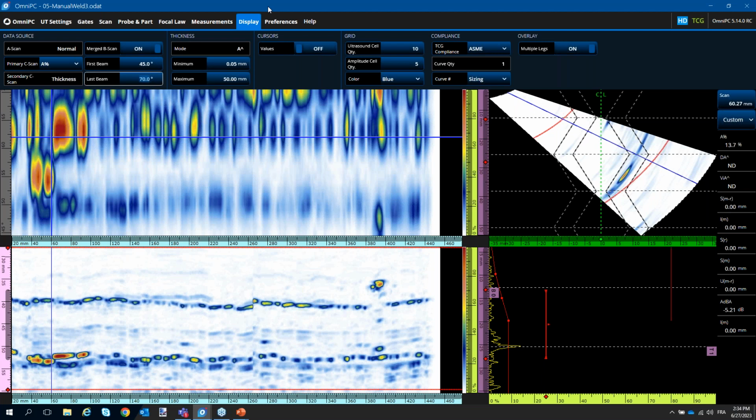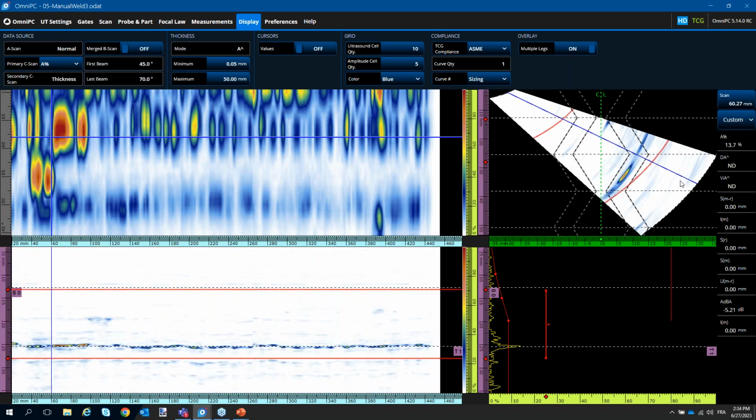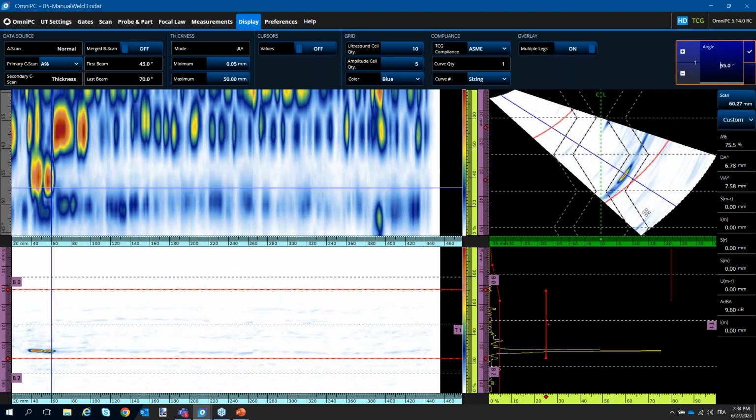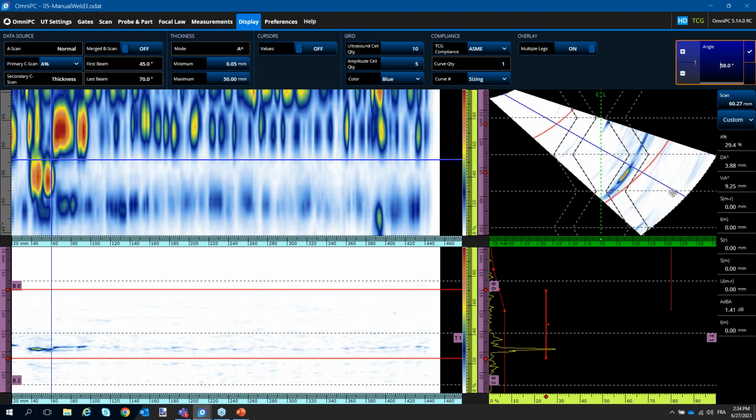So that's a limitation of the merge B: make sure that you're not leaving echoes that are hidden by one another, especially in the case of geometry echoes. One simple way to do it is either use the first beam controls, as we just demonstrated, or in any case, keep it with the active beam. Make sure you did not forget anything.